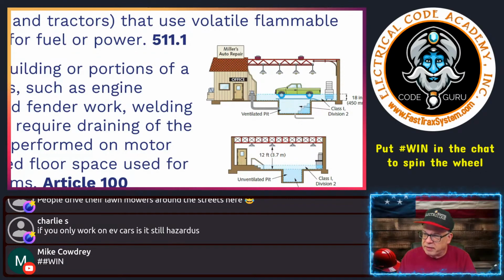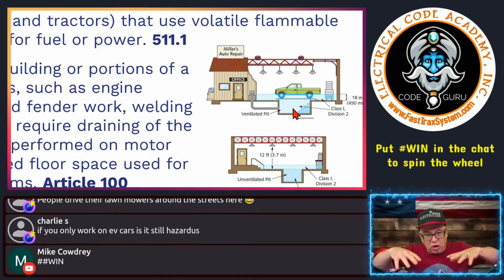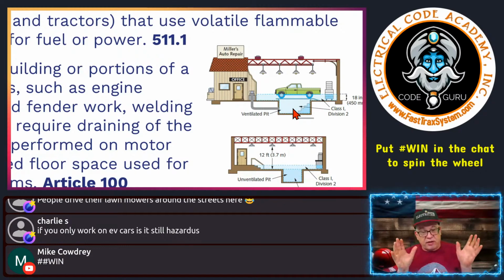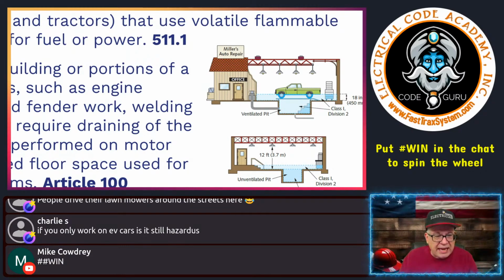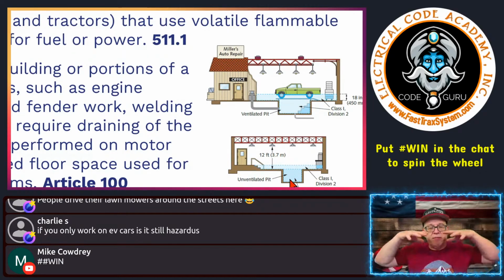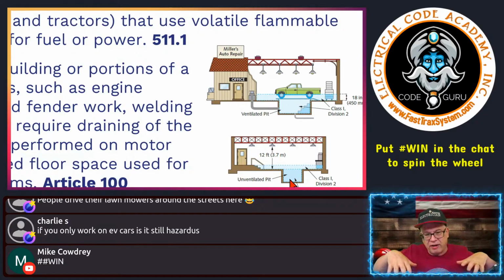You may have an area, depending on if this pit is ventilated - meaning it has 4 air exchanges per hour, keeping the levels low - then it's still a hazardous classified location, but not as problematic as this pit which has no ventilation. That means the gases are going to collect there, and if you drop a tool or something creates a spark, you got a problem.